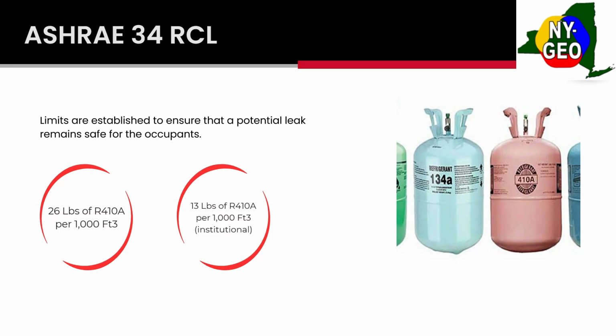So right now, 410A per 1,000 cubic feet in a commercial space is 26 pounds. In an institutional space, which has stricter requirements, it's only 13 pounds. So it's important to know the refrigerant concentration limit. This is the safety limit that counts for both toxicity and flammability. It's a broad safety measure that covers everything from respiratory health to flammability risk.